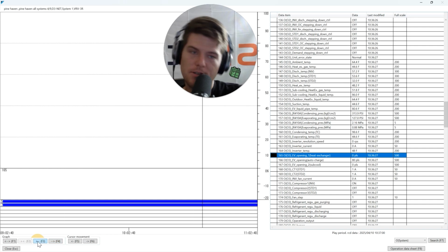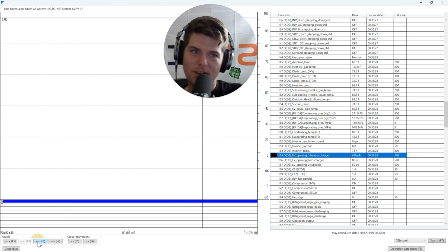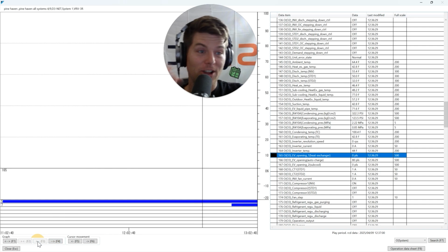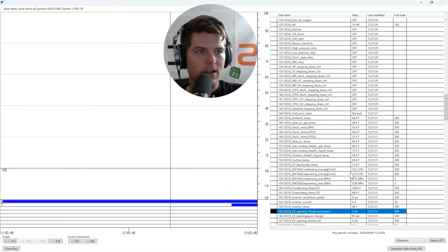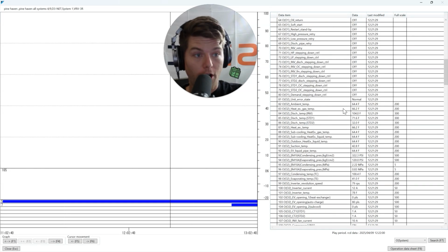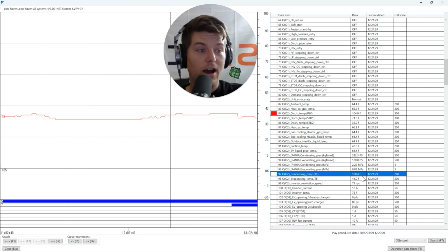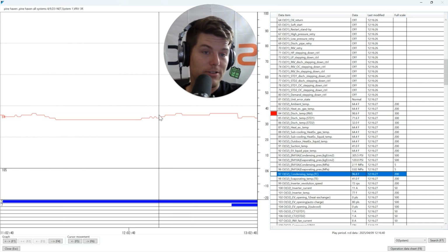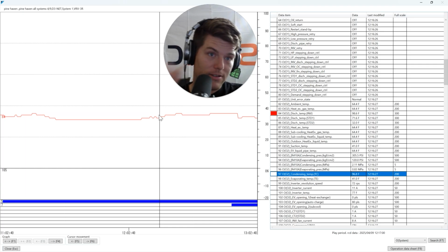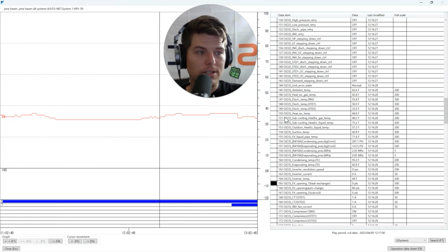So now the question is, let's play the game, where's the liquid refrigerant? And so now we're going to look at this module and see it's mostly at 0 pulses. And that's great. Let me go to a spot where everything else is complete and utter dog crap. Yes, I said dog crap because that's what this is. 104 degree discharge temp. Oh man, this makes me want to cry. And 100 degrees. So it's 4 degree discharge superheat. It's great. Loving it. Mint. If you squint, it's mint. All right, let's do this.